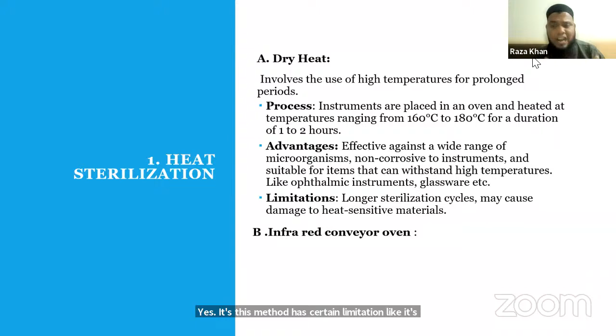This is cost-effective and effective against a wide range of microorganisms. It is non-corrosive to instruments and suitable for items that can bear high temperature. Commonly, we use this method for sterilization of ophthalmic instruments and glassware. This method has certain limitations: it requires a long sterilization cycle and may damage items which are sensitive to heat, material which cannot stand such high temperature.